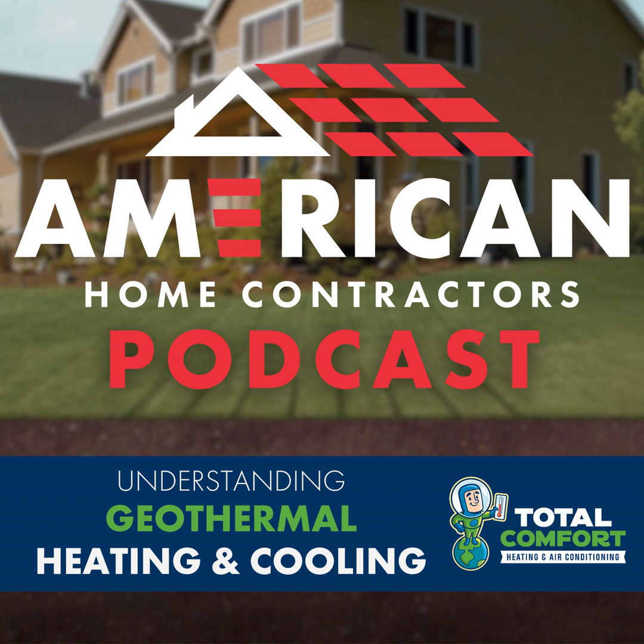Gotcha. So with geothermal, it's more efficient because you're taking the warmth of the ground, which is 53 to 55 degrees, right? And you're turning it into 70 degrees, give or take, inside the house, right? So that delta is a lot different than if it's 10 degrees outside in the winter or 95 degrees out in the summer. So that's why it's more efficient, just taking a different temperature difference.